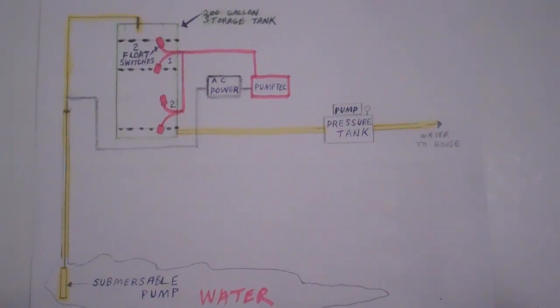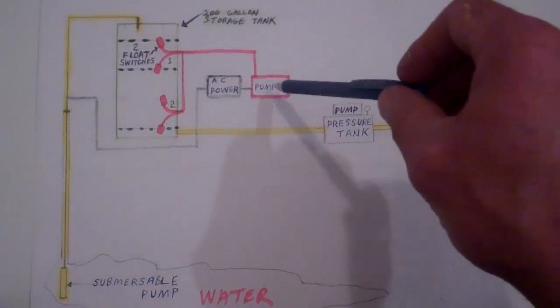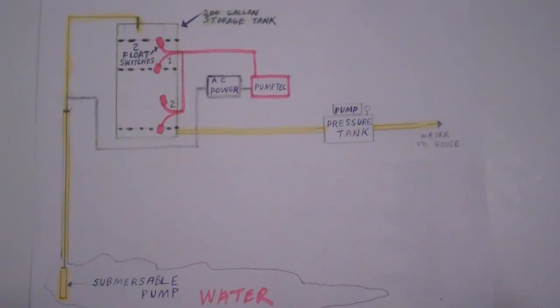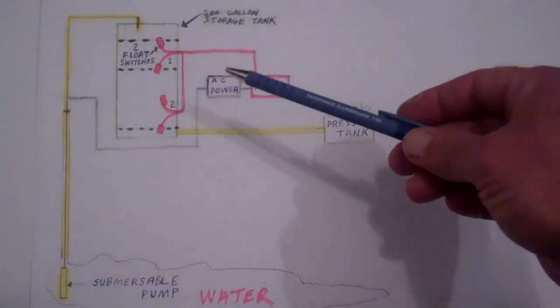So then what happens is the unit itself, the Pumptec, has a timer that can be set on it. The one that I have is anywhere from two minutes to two hours. I have mine set to two hours. So once it senses that the water level in the well is low, it'll stop pumping, and then two hours later it'll kick in.